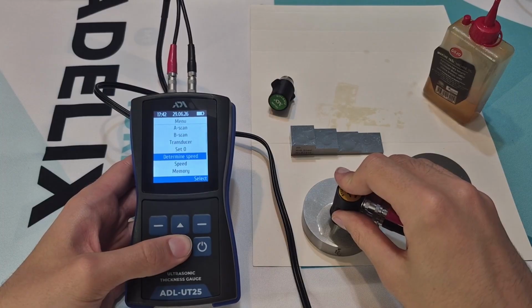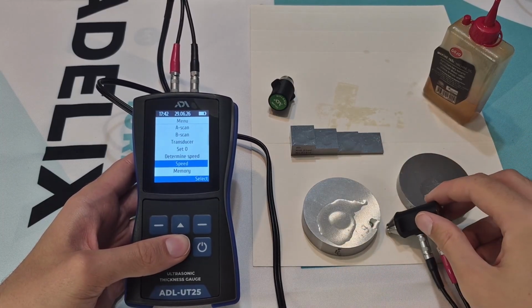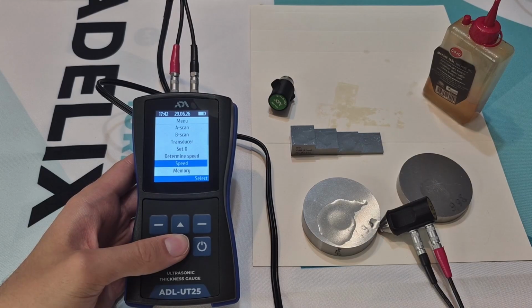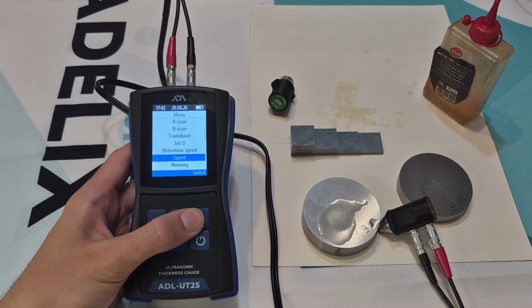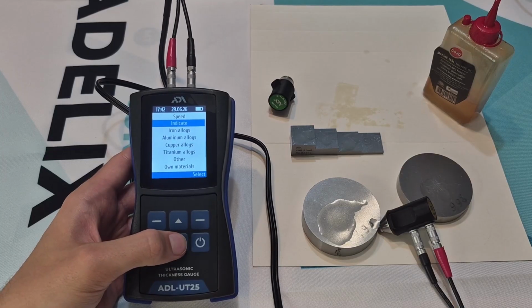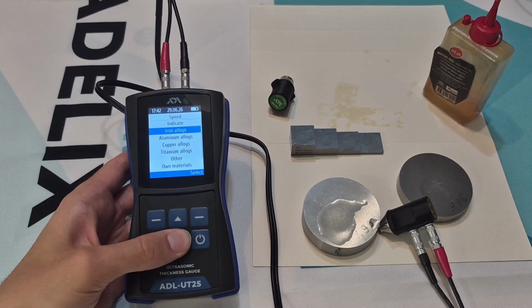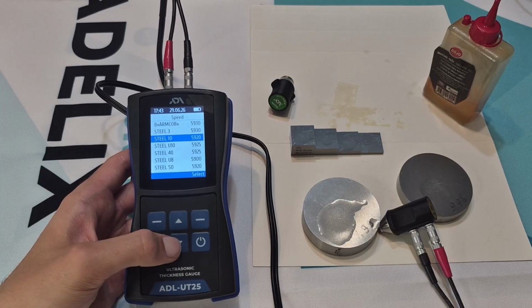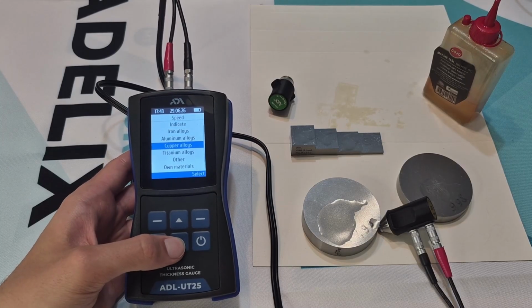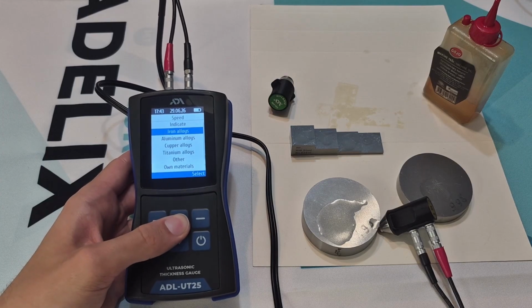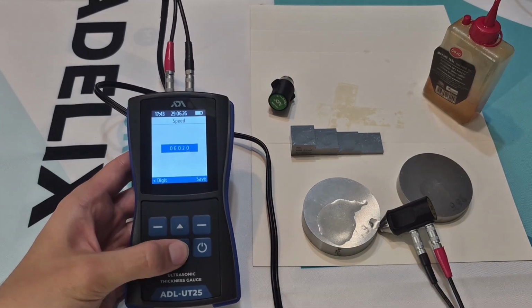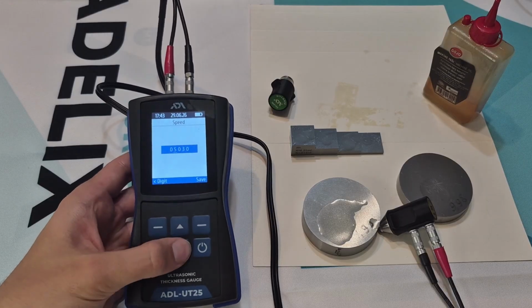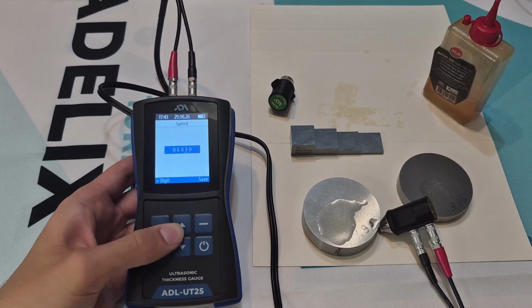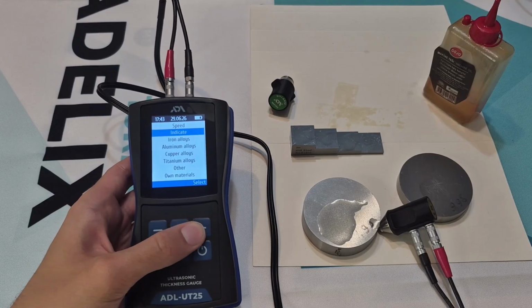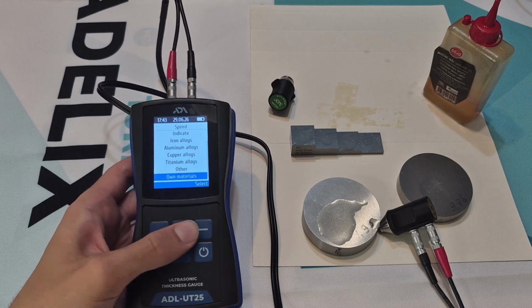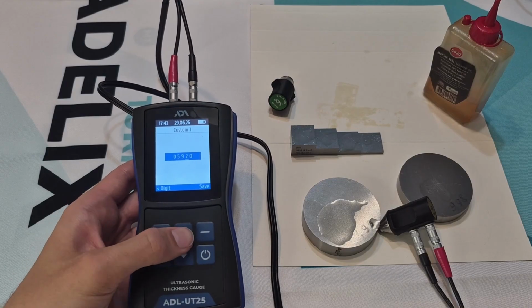We have already covered the zero calibration and velocity determination functions. If the ultrasonic velocity is unknown, the built-in material library can be used. It includes steel, aluminum, copper, titanium, and many other materials. After selecting a material, the device will automatically set the corresponding ultrasonic velocity. If needed, the velocity can be set manually. If the required material is not in the library, it can be added manually. To do this, we go to the My Material section, press Select, then Change, enter the required velocity and save the material. After that, it can be quickly selected from the list.